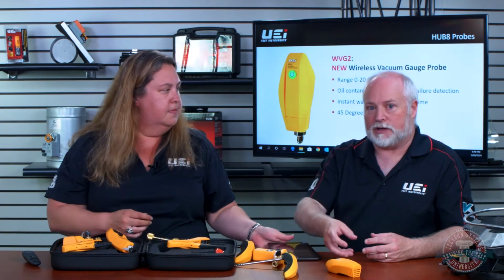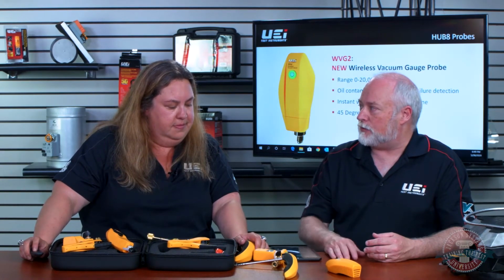So even if it's the winter time and you're putting that system in, knowing that you've pulled down to a vacuum and you're getting the moisture out of that system helps. The other thing that can help you do is determine, and you've got a leak rate scale on here and so forth, how quickly that vacuum rises when we shut off our pump, to find out, hey, do we have a leak still in the system? Or do we still have some moisture left in it? So that's all built into the app to allow you to check that, monitor that.